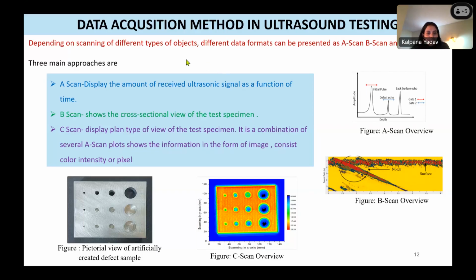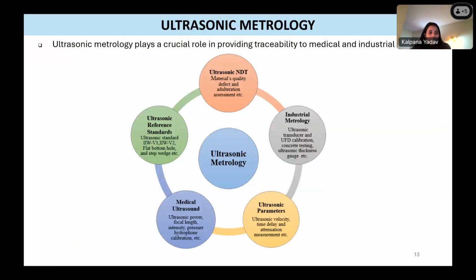But here you see a pictorial view of an artificially created defect sample that I made for the C scan testing. A C scan display is going to be a 2D scan of the plane. If you see here, an artificially created sample, and the right side shows the C scan overview. So this is a C scan. You can see how the defect is oriented in the sample. So if you want to know in more depth what your defect is like and what its orientation is, you can do a C scan for a better evaluation.